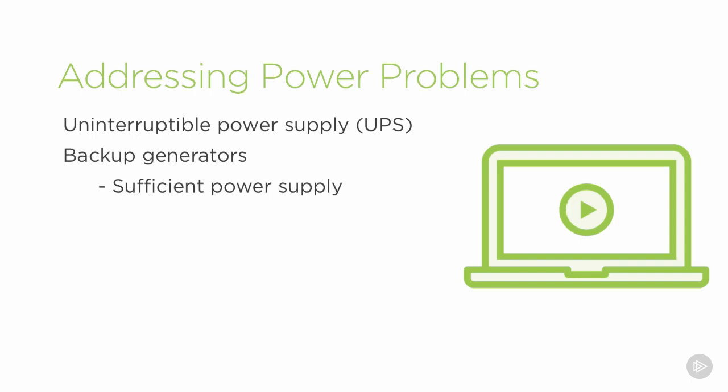When we talk about carrying the load, remember it's not just the IT equipment. We also need enough backup power to run the air conditioning system, because if the A/C doesn't work, equipment failure will follow very quickly. Make sure backup generators are run maybe once a month, are properly maintained, and have a supply of fuel that isn't getting too old.